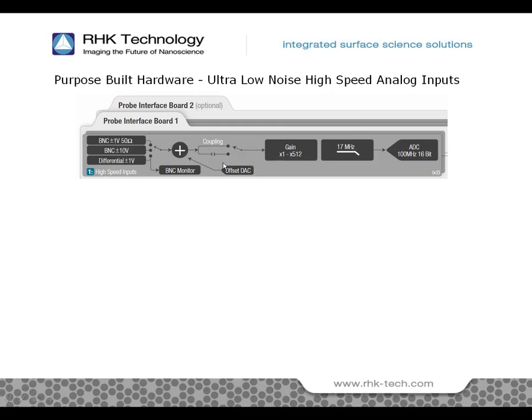In addition to a high bandwidth, these input channels provide programmable gain to allow even the smallest signals to be accurately measured. Even with the gain set to its maximum value of 512, the input bandwidth remains undiminished. These input channels also have programmable input offsets, which allow offsets in the input circuitry or from the preamplifiers to be nulled down to exactly 0. In the past, you often needed to stand on a ladder and adjust the offset of the preamp with a screwdriver. These high-speed channels allow the selection of standard BNC inputs or impedance-matched differential inputs that connect to our matching preamplifiers. These differential inputs provide optimal performance for low-level and high-frequency signals.